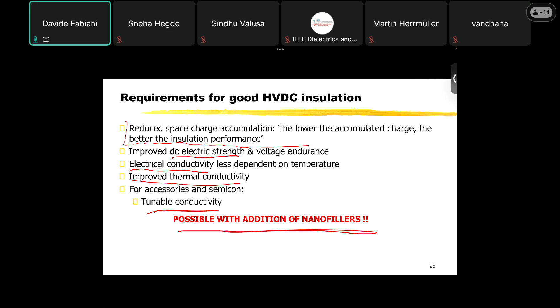So what are the requirements for good HVDC insulation? I've spoken a lot about space charge accumulation, which should be reduced — the rule of thumb is the lower the accumulated charge, the better the insulation performance. But we also want improved DC electric strength and voltage endurance, or an electrical conductivity less dependent on temperature. This is important because it can reduce electric field variation inside the material with temperature, or improve thermal conductivity for accessories and semicon material, having for instance a tunable conductivity. All these things can be done by adding nanofillers to our electrical insulating material.